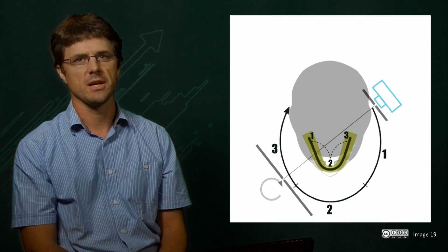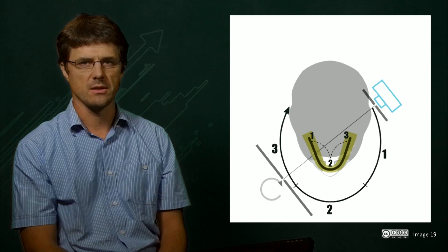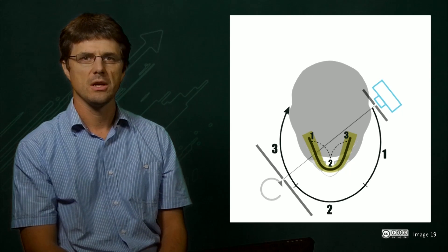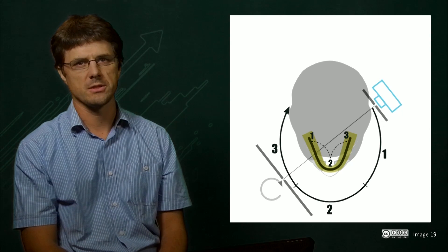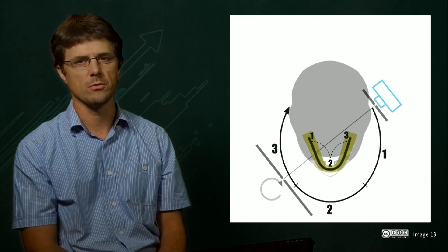Note that the imaging plane is now thinner at the front for the incisor teeth and thicker for the molars. This sort of plane is only possible by the combination of multiple axes of rotation and varying the film drum speed.